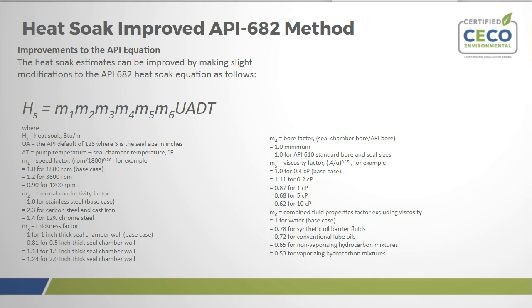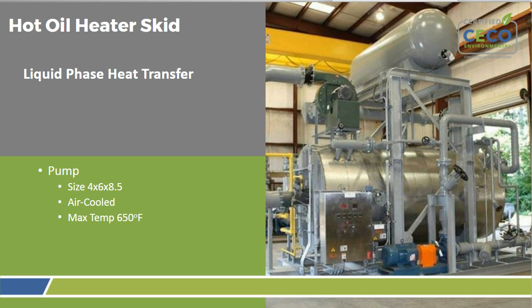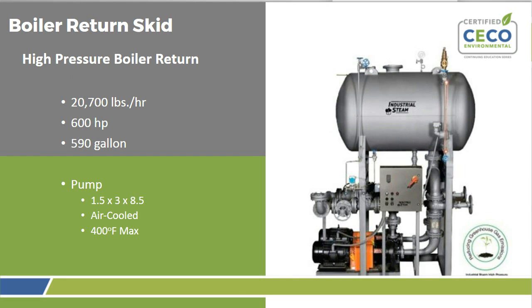And just a few quick items. This is a typical high temperature heater skid that you can see. This is a heater unit that is used to increase the temperature of hot oil, and then that oil goes off into your process to do whatever it needs to do. The pump in this case is a 4x6x8.5. It's an air-cooled max temperature of about 650 degrees. This is a high-pressure boiler return, the unit itself is operating about 20,000 pounds per hour. The pump is a 1.5 3, 8.5 with an air-cooled 400 degrees max.